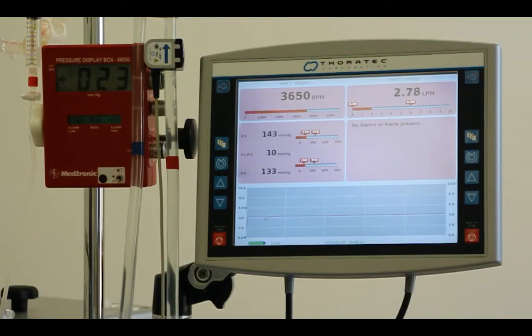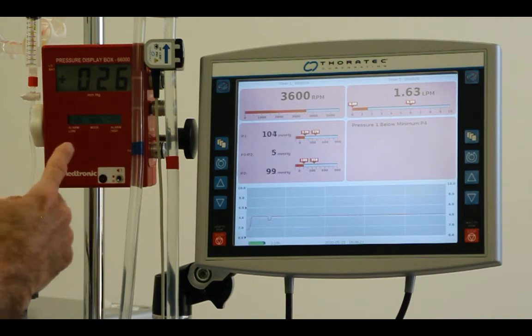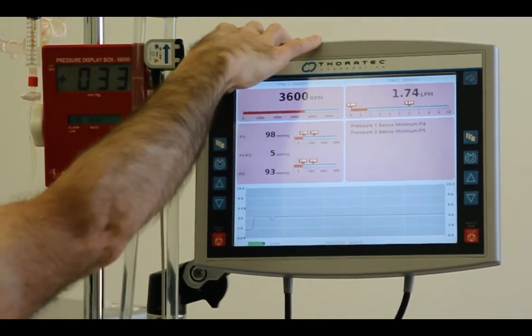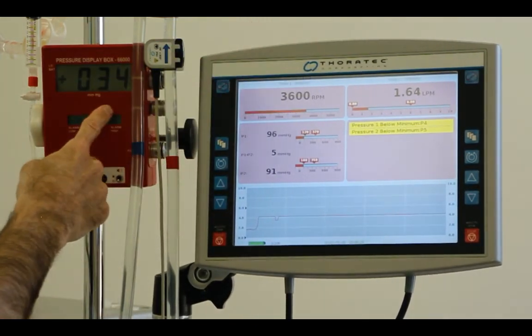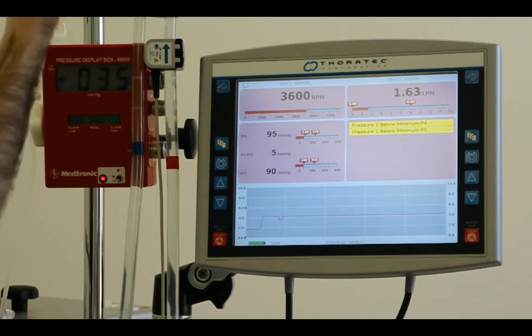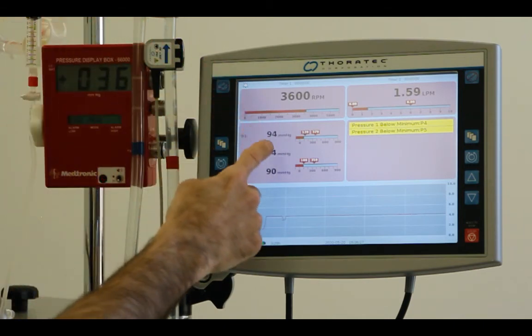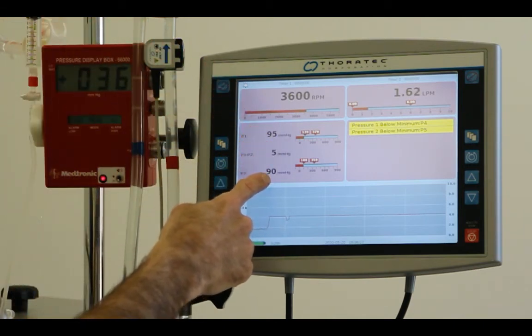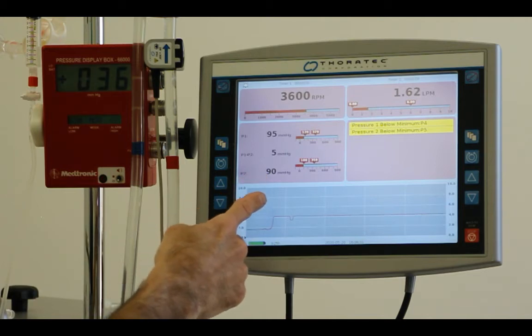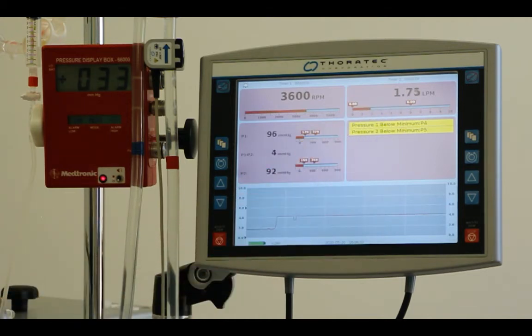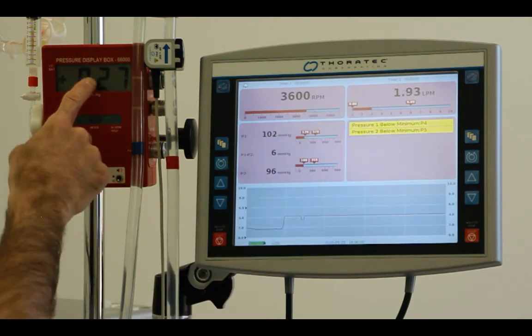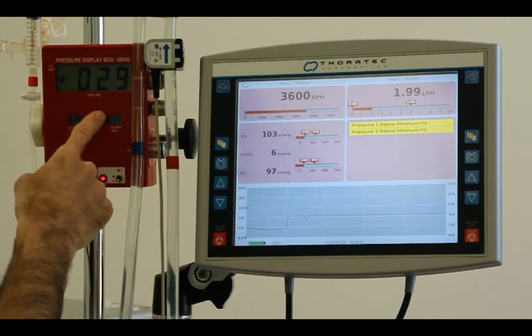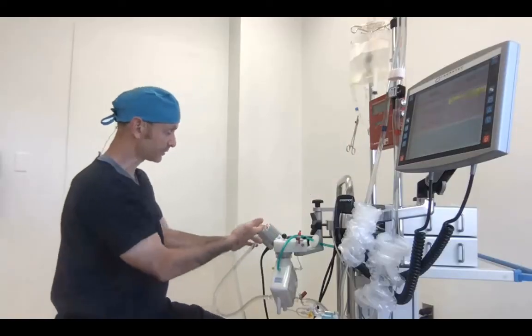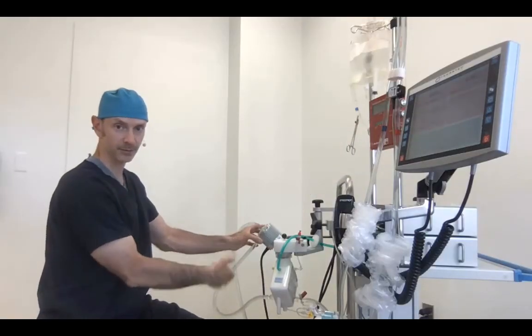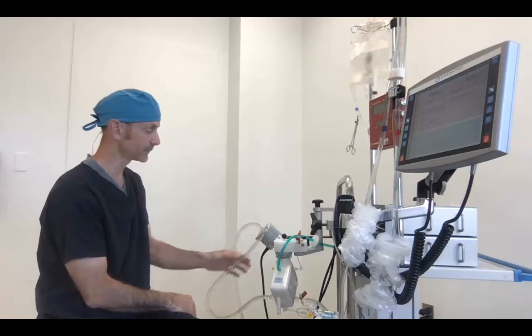We're going to kink this right here and watch. The venous line pressure became more positive. The oxygenator's pressures became less positive, and the flow came down. So this says it's not in the arterial line. And this one says it's not on the venous line, so the place left over is that gap in between the venous and the arterial line.